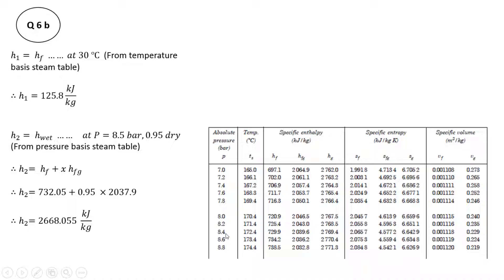From the pressure-basis steam table, values are available at 8.4 and 8.6 bar, so we take the average for 8.5 bar. At 8.4 bar, HF is 729.9, and at 8.6 bar it is 734.2, giving an average HF of 732.05 kJ per kg. Similarly for HFG: 2039.6 plus 2036.2 divided by 2 gives 2037.9 kJ per kg. With dryness fraction x = 0.95, H2 = HF + x·HFG = 2668.055 kJ per kg. This gives us the specific enthalpy of water entering the boiler and the specific enthalpy of steam generated.